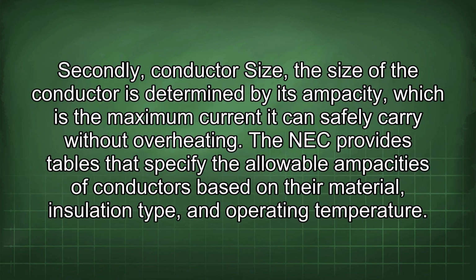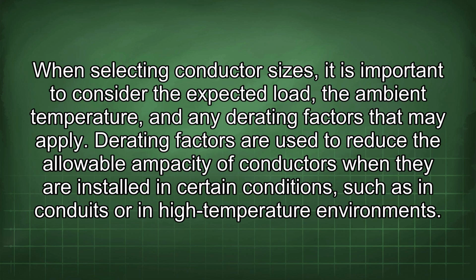Secondly, conductor size. The size of the conductor is determined by its ampacity, which is the maximum current it can safely carry without overheating. The NEC provides tables that specify the allowable ampacities of conductors based on their material, insulation type, and operating temperature. When selecting conductor sizes, it is important to consider the expected load, the ambient temperature, and any derating factors that may apply. Derating factors are used to reduce the allowable ampacity of conductors when they are installed in certain conditions, such as in conduits or in high-temperature environments.